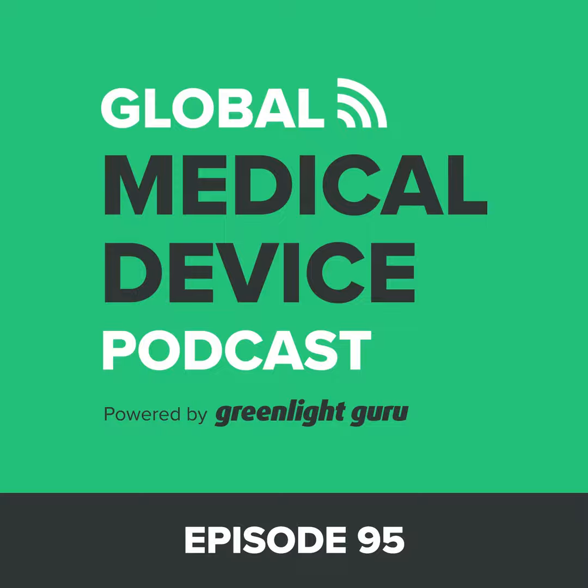User error produces blame on the user, but use error means that it's designed in a way that the adverse event might have been predictable, that it was preventable, that it's not the user at fault, but the manufacturer might be responsible for designing and labeling the device in a way that promoted the error, that was inadequate in design. And I think that's where you get the scare factor of, oh my goodness, this is a problem.